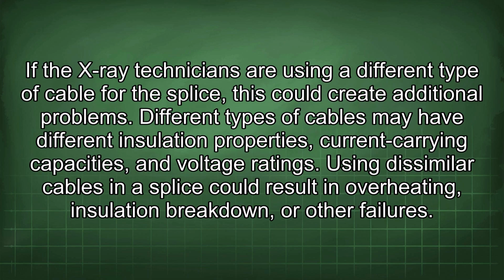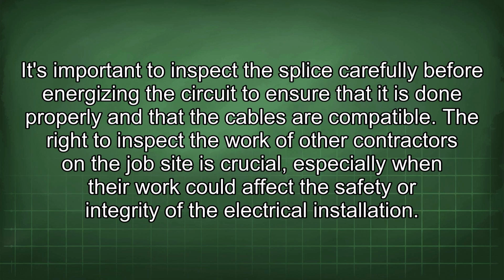If the X-ray technicians are using a different type of cable for the splice, this could create additional problems. Different types of cables may have different insulation properties, current carrying capacities, and voltage ratings. Using dissimilar cables in a splice could result in overheating, insulation breakdown, or other failures. It's important to inspect the splice carefully before energizing the circuit to ensure that it is done properly and that the cables are compatible. The right to inspect the work of other contractors on the job site is crucial, especially when their work could affect the safety or integrity of the electrical installation.